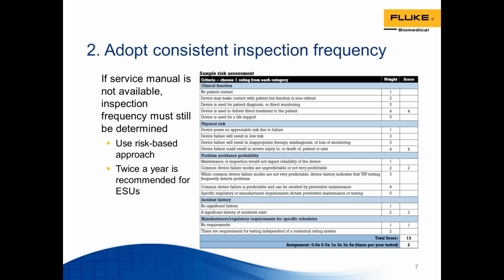When we use this approach, the column called score is summed up, and at the bottom you'll see the total risk score on the row above the last one. Twice a year is what's recommended for electrosurgery units, and twice a year is what we came up with in this. The 13 or higher means twice per year.